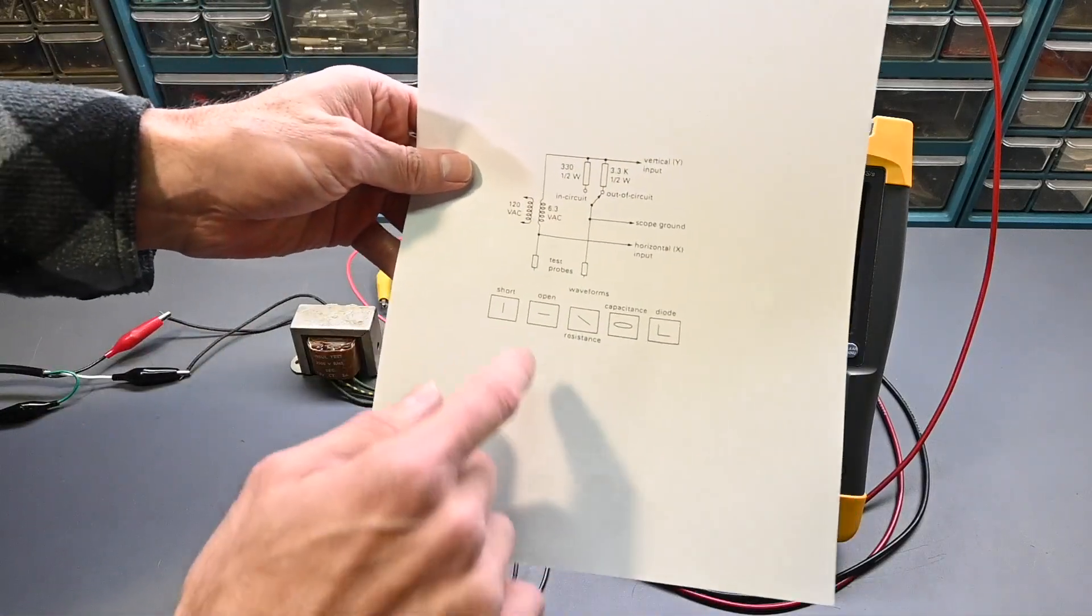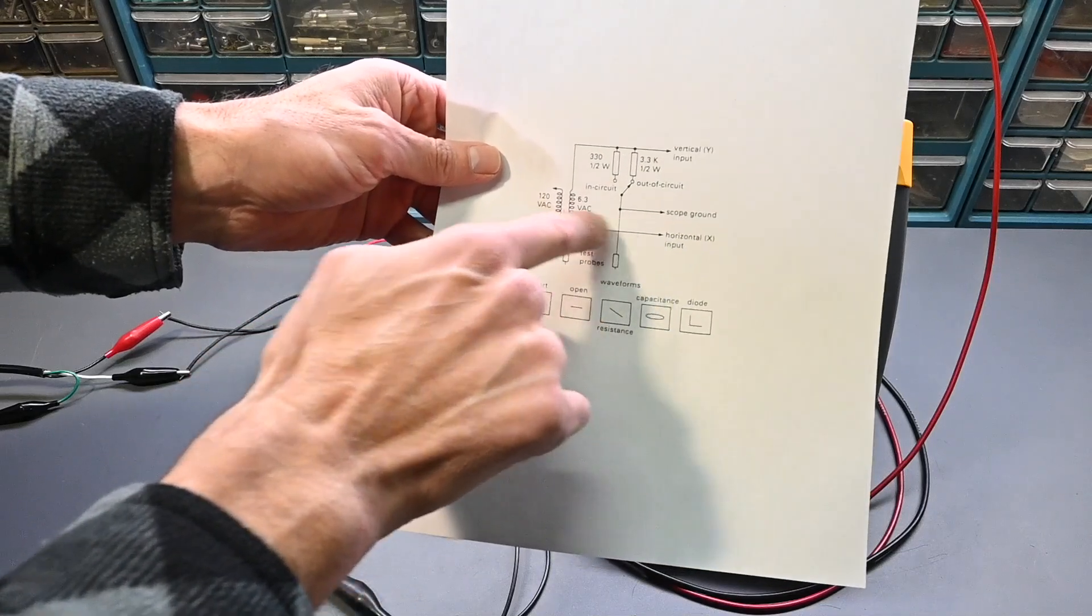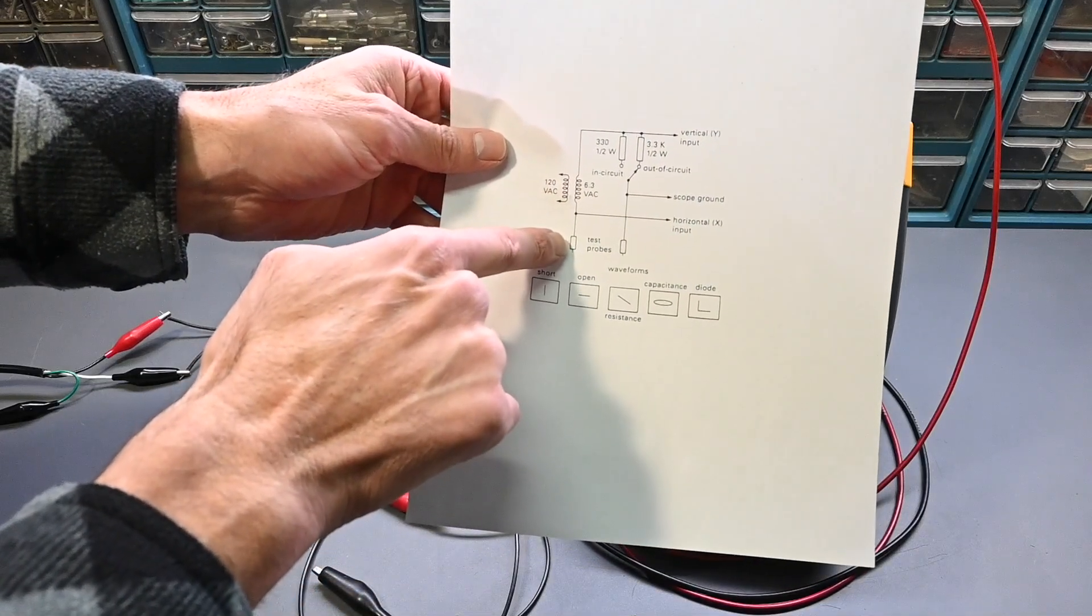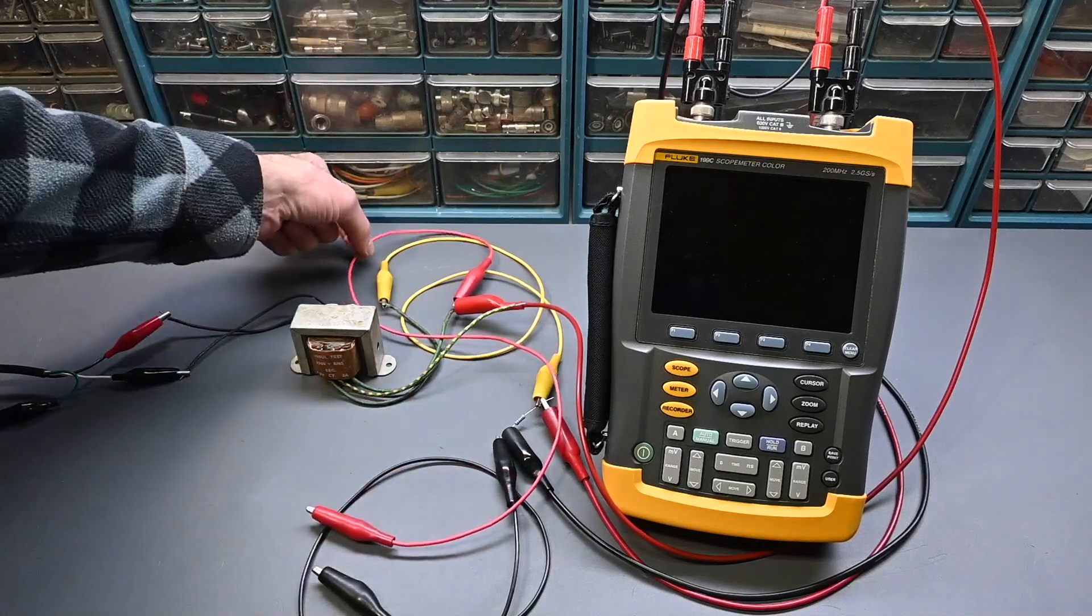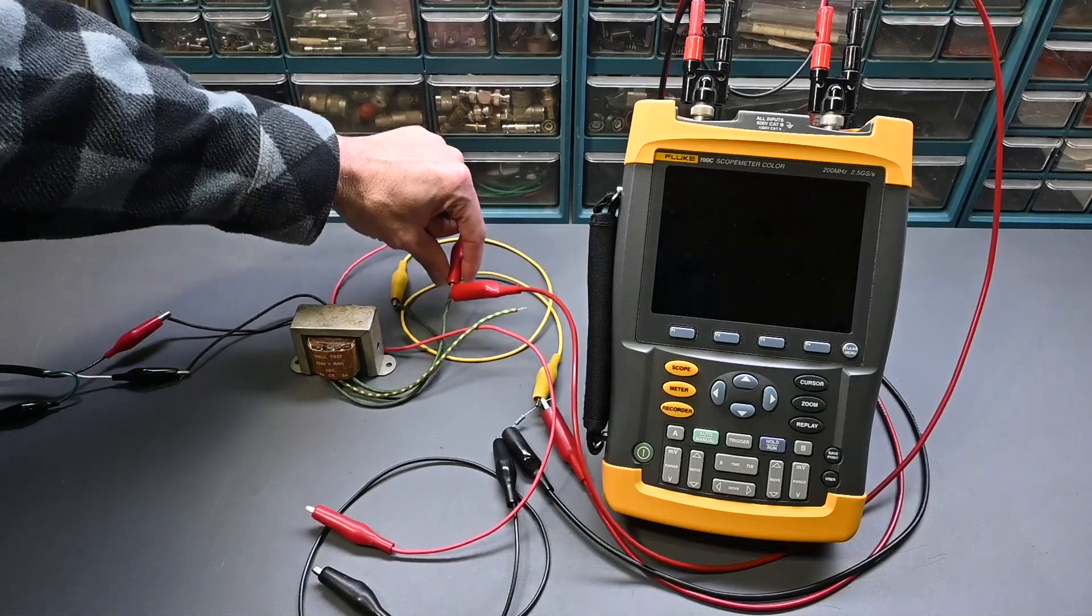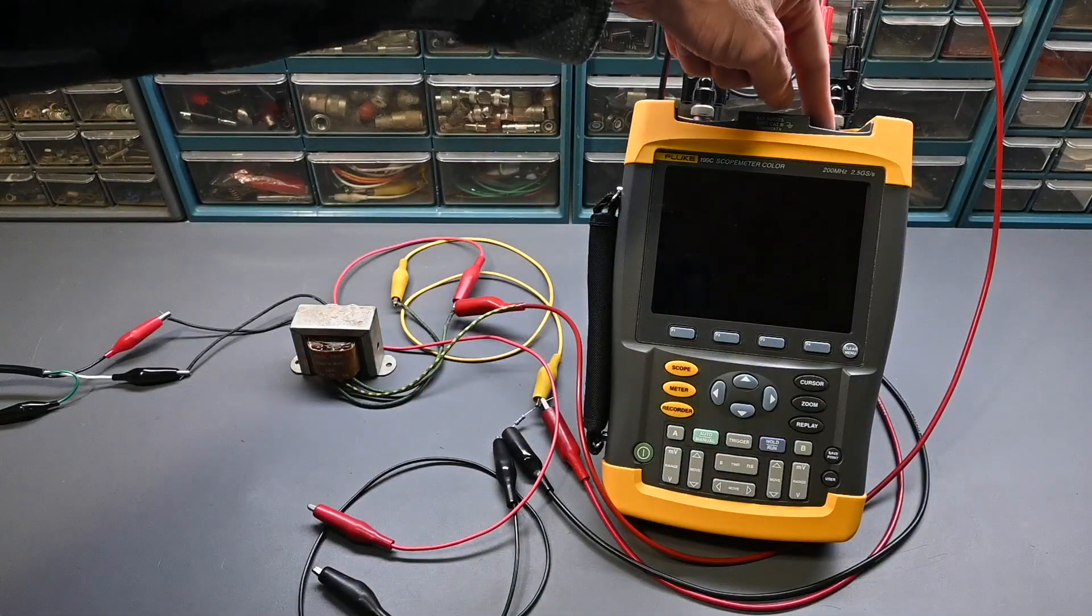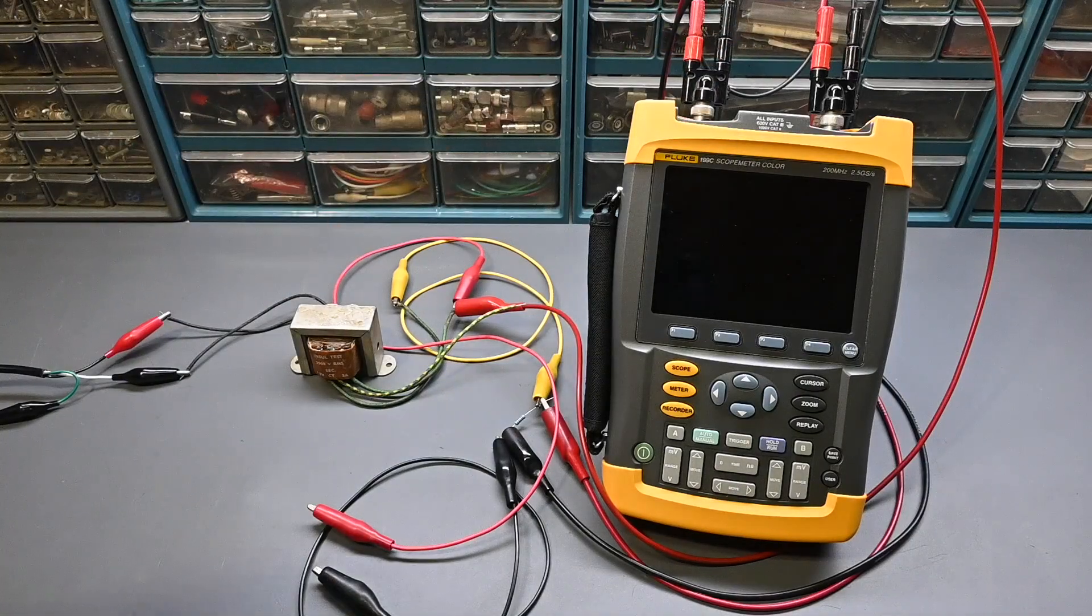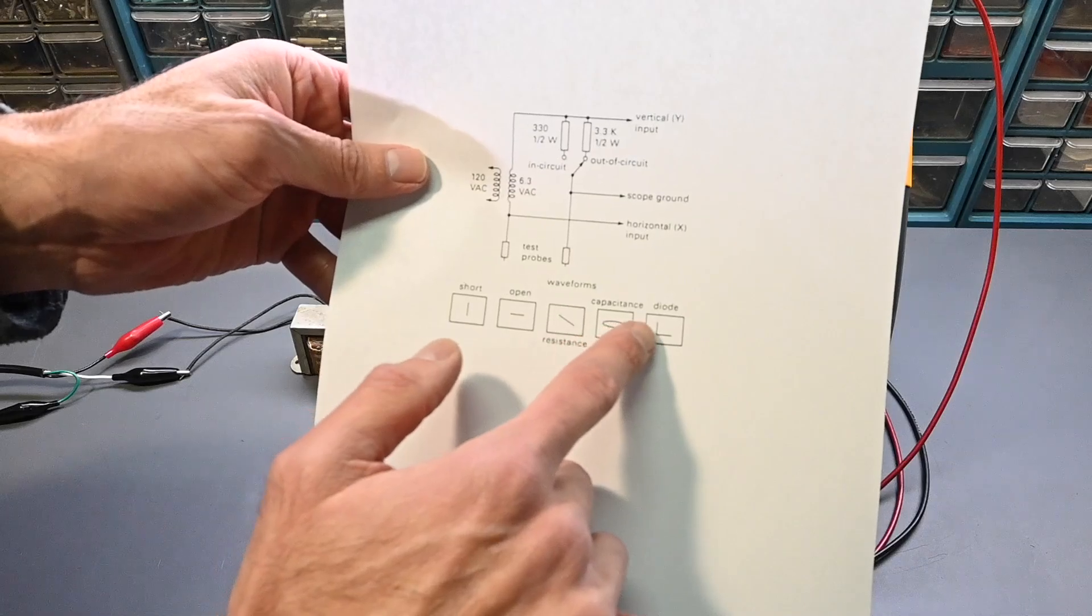Looking at the schematic again, the other side of the transformer goes to the horizontal or X input on the oscilloscope and comes down to the other test probe. These patterns you can see down here are the displays we'll be seeing on the oscilloscope. When we have a short circuit, there is a vertical line. An open circuit is a horizontal line. Resistance ends up being some type of sloping line between these two extremes. Capacitance is an open circle. In a diode, you see this L shape. If you test a Zener diode, you'll see another knee in that L shape. We can also test inductors, where instead of having the circle going around on the horizontal axis, you'll see it more on the vertical axis.